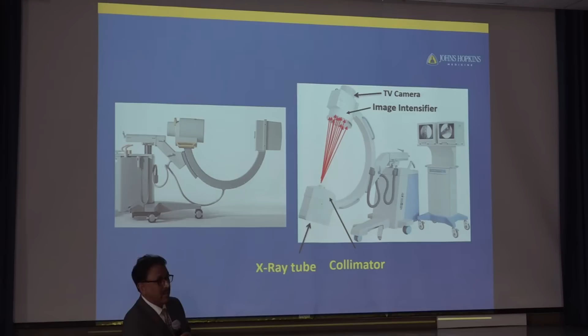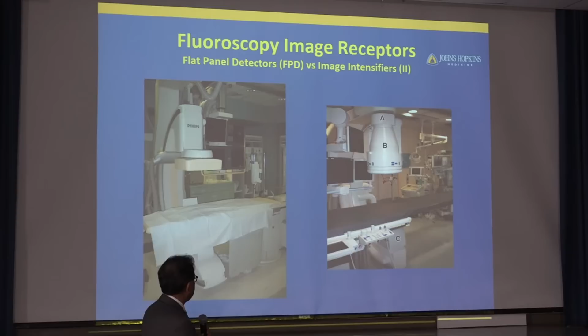Then over the past 10 years, the systems slowly moved towards digital. Now, instead of big image intensifier boxes, we have what is called a flat panel. It is a digital detector, and it gives a lot more versatility to move around the patient. At the same time, when it is optimally set, it gives a lot less radiation for the same type of image quality. So flat panel detectors have now pretty much become common everywhere.